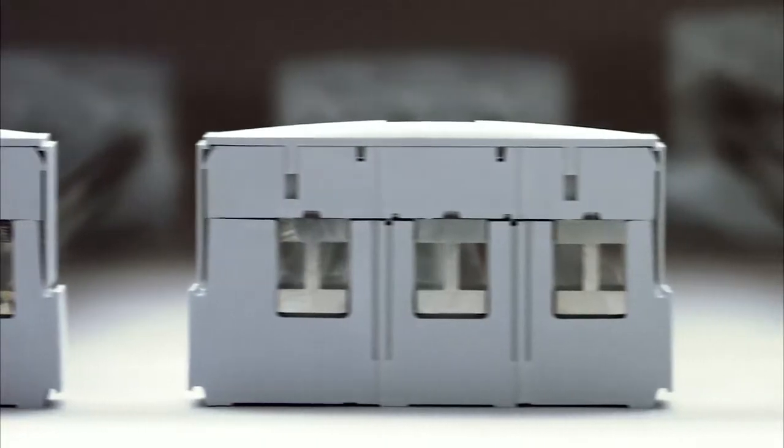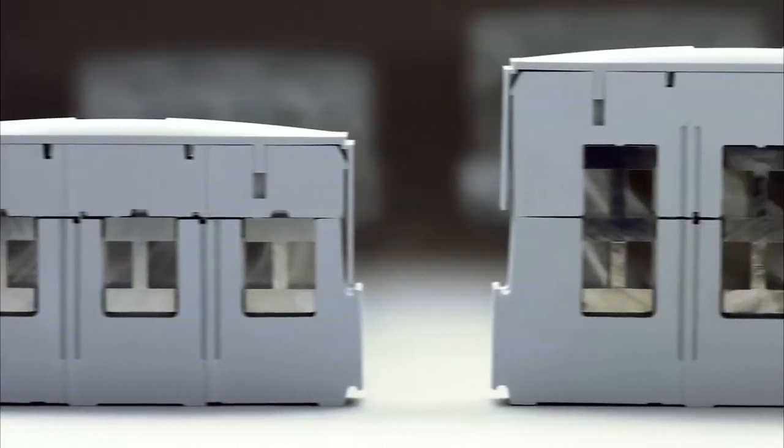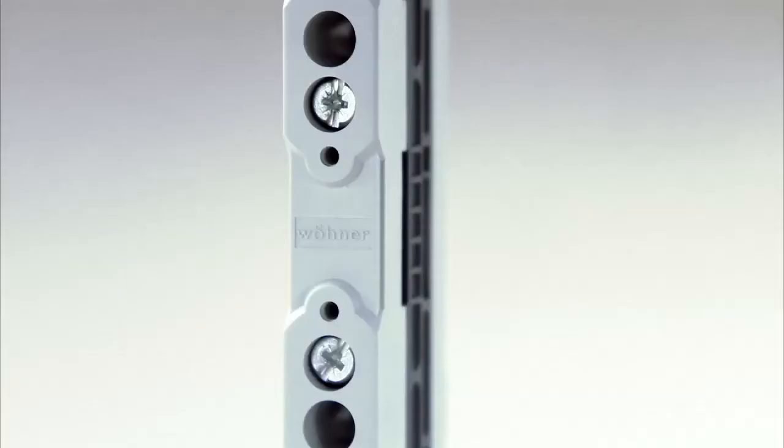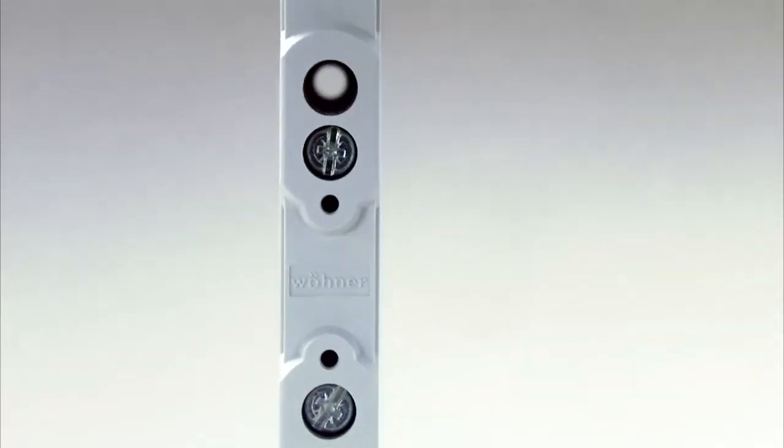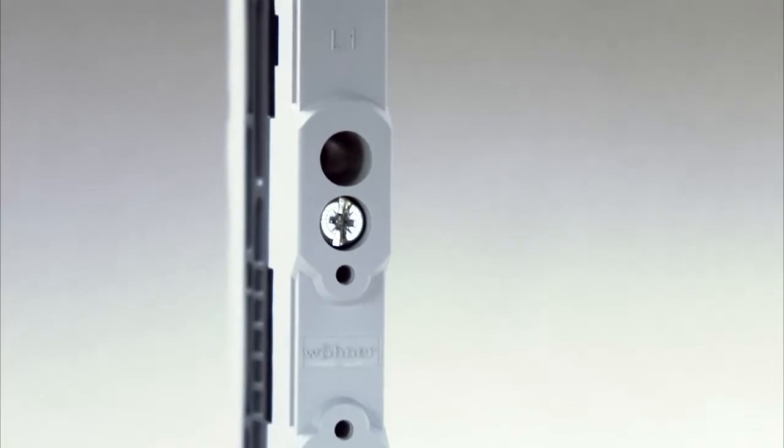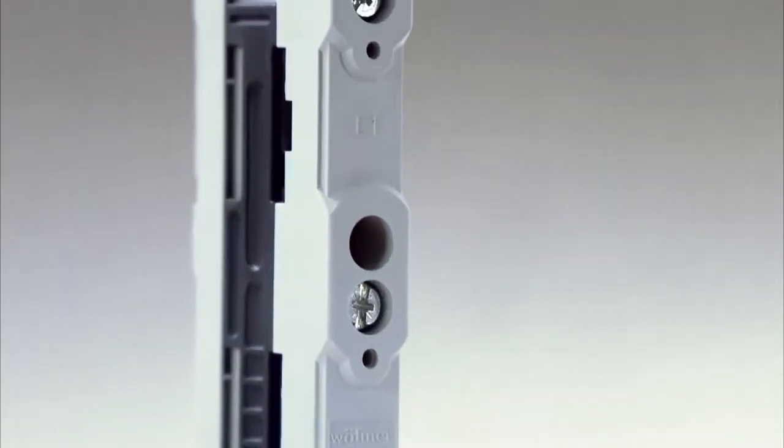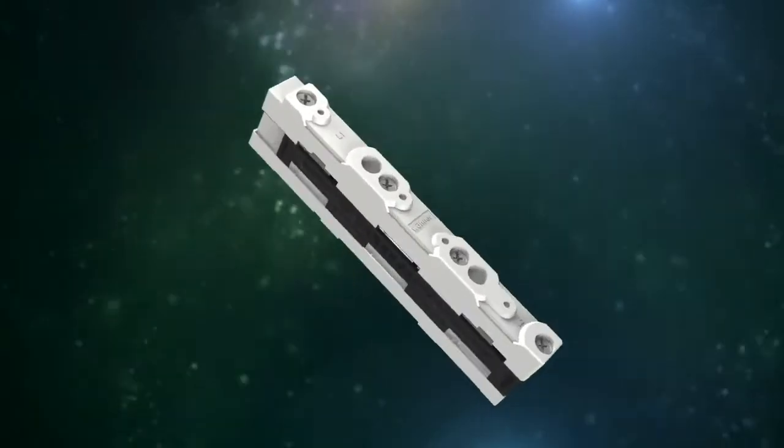These are supplemented by Wöhner special profiles such as the double T, triple T, and TCC profile for high power requirements. This enables currents of up to 2500 amps to be carried safely.